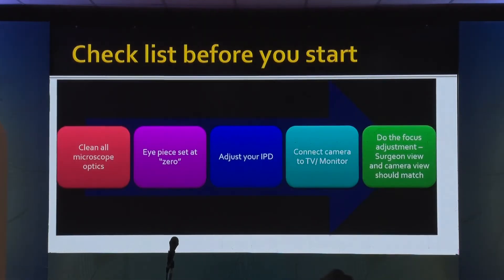Before you start, first clean all your microscope optics. Set your eye piece to zero. Adjust your IPD. All these things need to be done. Then connect your camera to a TV or monitor and adjust the focus. What is important is that your eye focus and the camera focus should be the same. If they are not the same, you will be viewing correctly and focused while your recording will not be good.